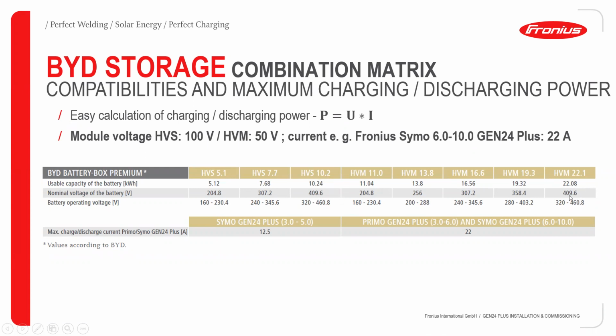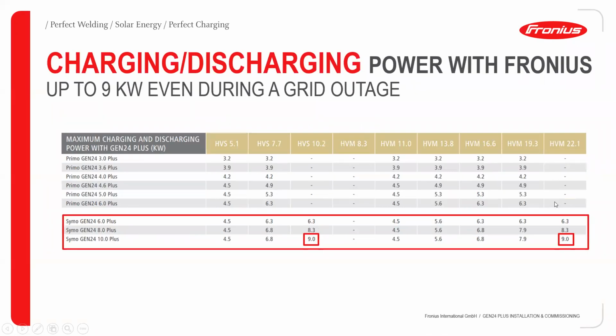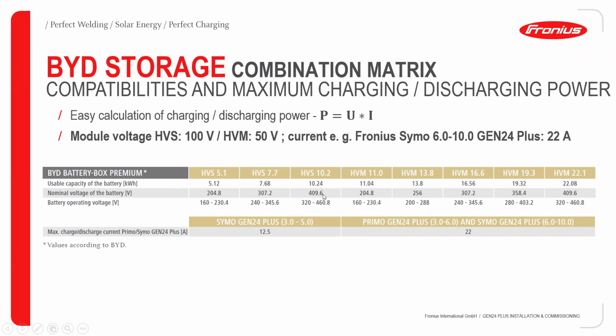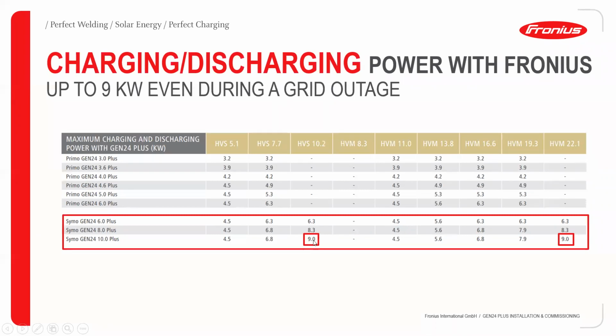So that's how these figures actually come about. By the time you multiply 409 volts times 22 amps obtainable for the Primo 3 to 6 and Symo 6 to 10 kilowatt ranges, you get 9 kilowatts of power. That's a very remarkable figure, because there are very few products that can give you this power for charging and discharging of inverters in the market. So for the HVS and HVM, you can get up to 9 kilowatts of both charging and discharging power with the Fronius inverter.